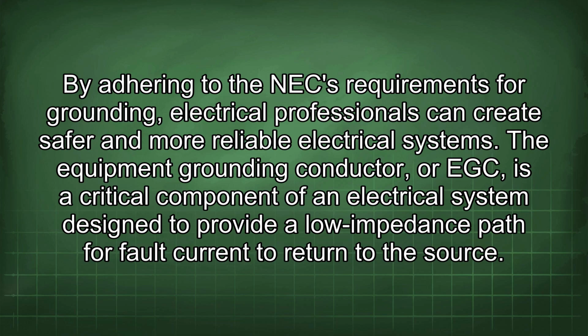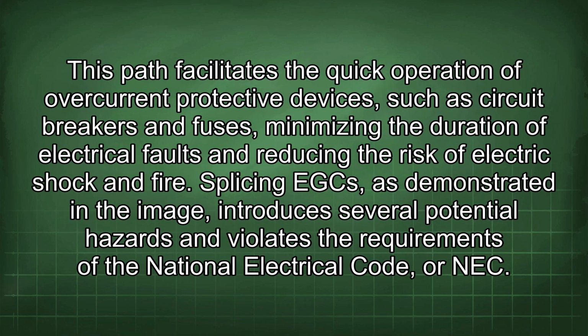The equipment grounding conductor, or EGC, is a critical component of an electrical system designed to provide a low-impedance path for fault current to return to the source. This path facilitates the quick operation of overcurrent protective devices, such as circuit breakers and fuses, minimizing the duration of electrical faults and reducing the risk of electric shock and fire.